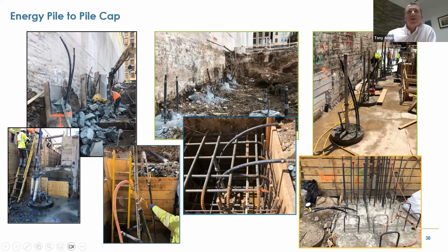Again, you can see here the next stage: piles being excavated, geothermal loops being exposed. Key next step is flush test, pressure test, running loops back to the sub-manifold location. Again, flush test and pressure test prior to concreting the pile caps in this particular case.